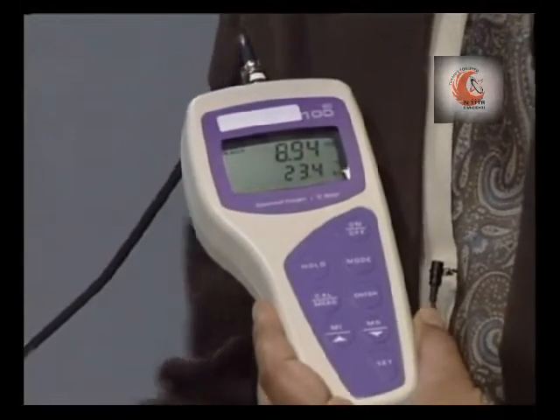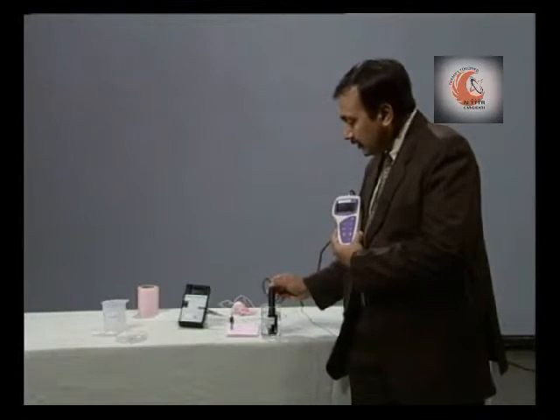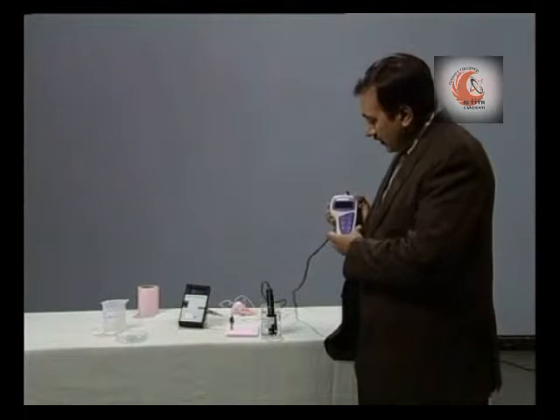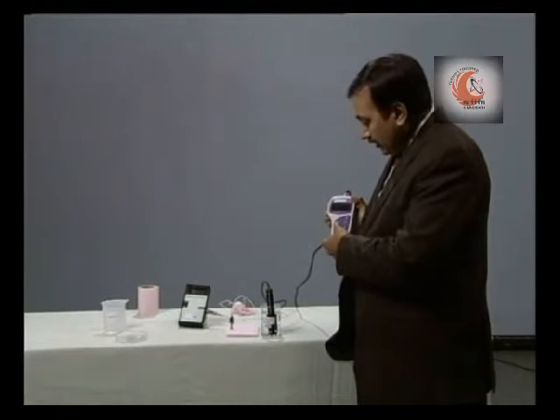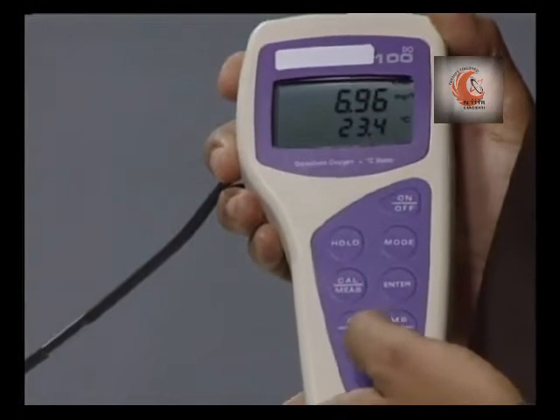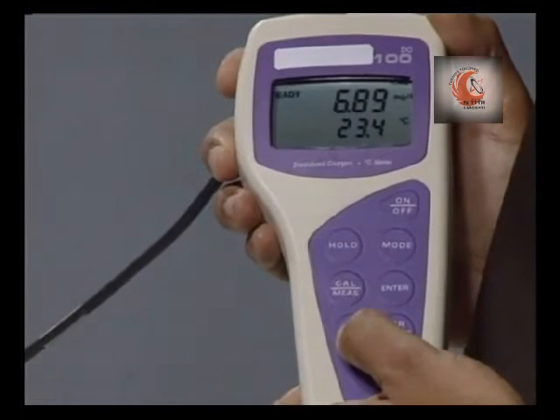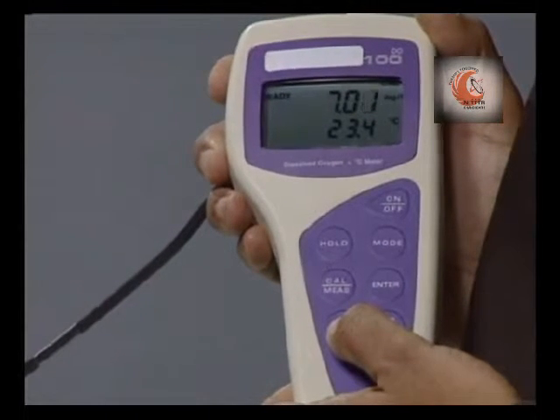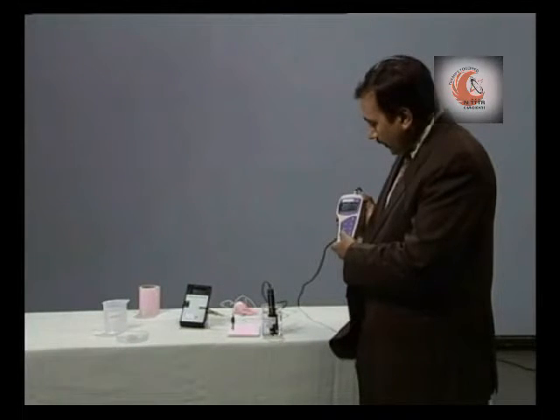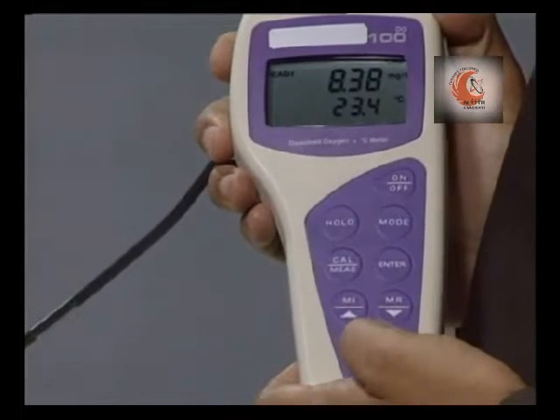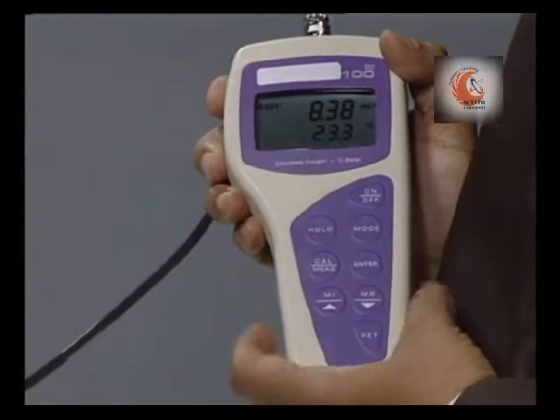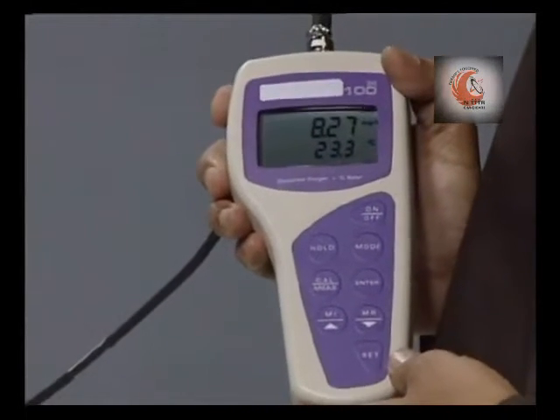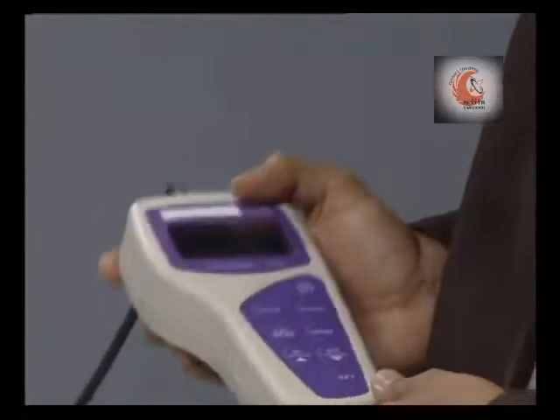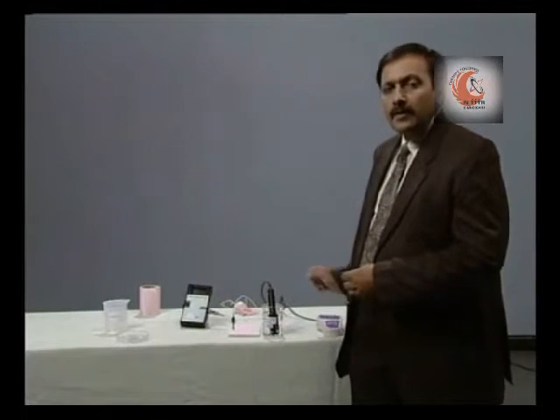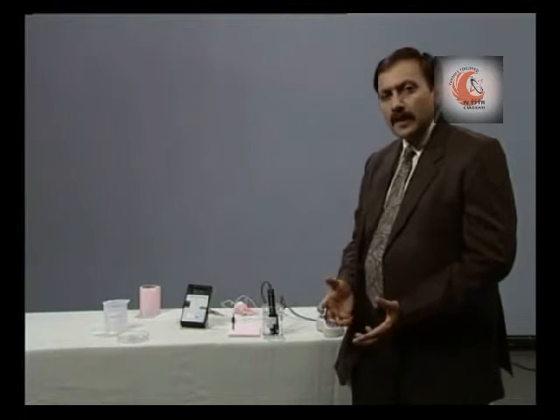Now put the DO probe in the deionized water. Bring the instrument in calibration mode and adjust the value to 8.38. Now press enter. And now the instrument is calibrated for DO mode as well. Now we can measure the dissolved oxygen of any sample with this instrument.